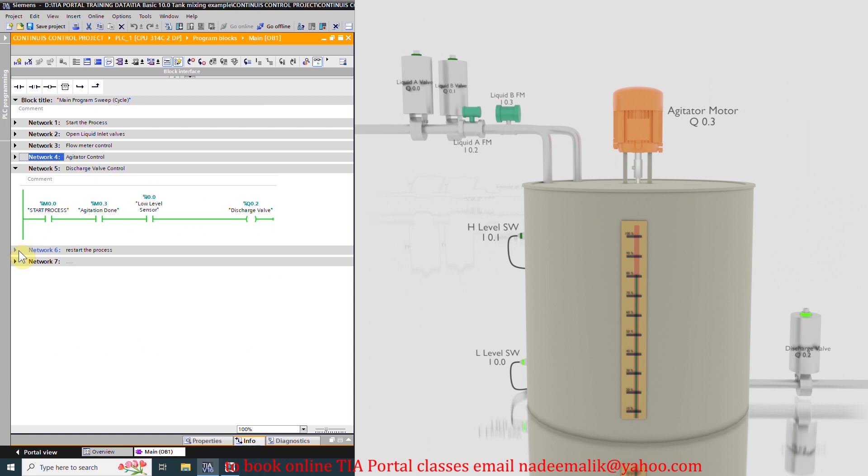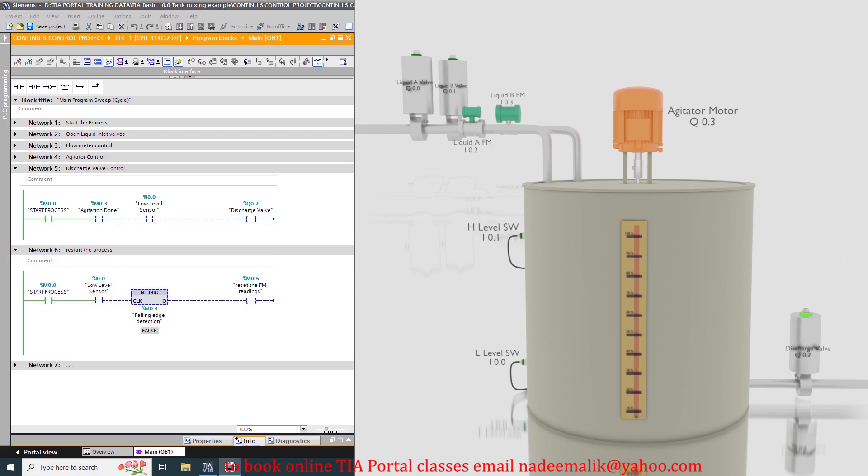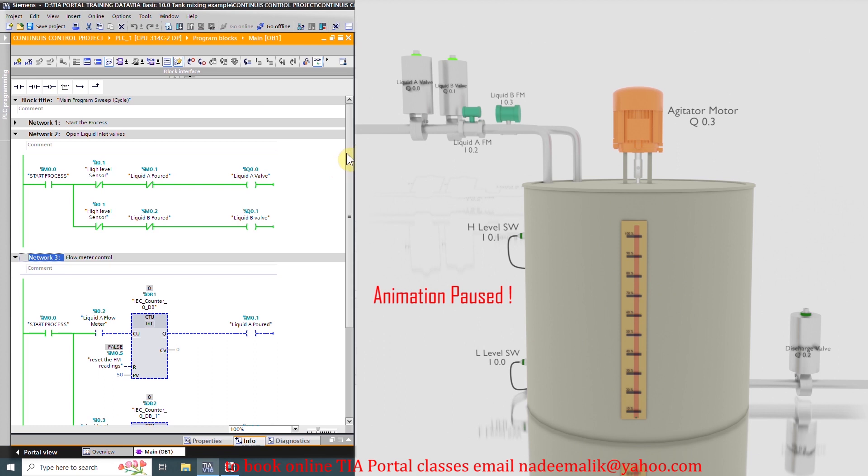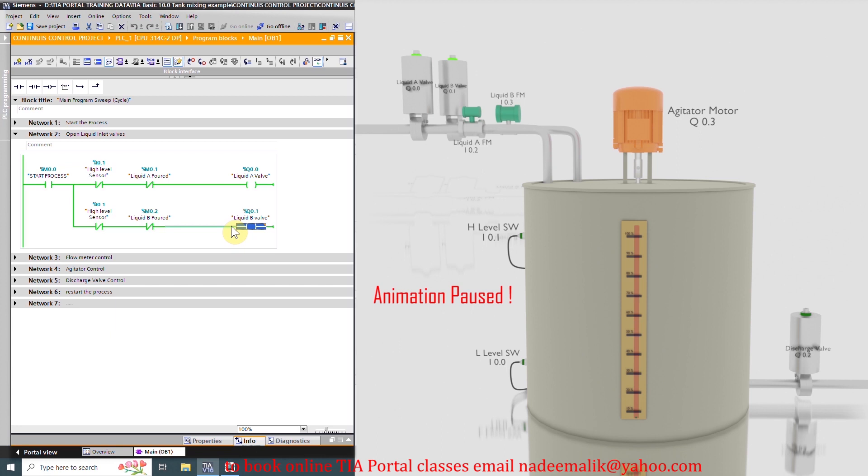As the liquid level falls less than the low level limit, it closes the discharge valve. And on the falling edge of the low level sensor I0.0 signal, it resets both counters to 0 liters and opens both inlet valves A and B to start filling again. And the whole process will repeat itself again.